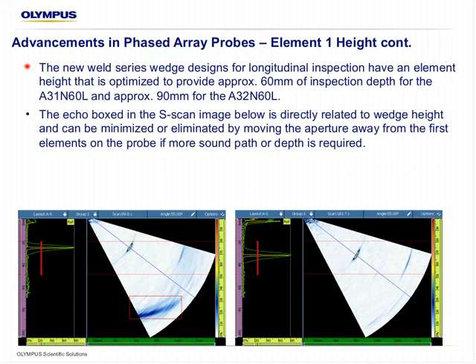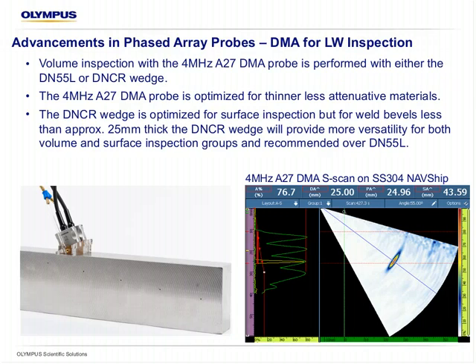The new Weld series L-wave wedges are designed to have an element height that is optimized to provide a 60-millimeter inspection depth for the smaller A31 probe and a 90-millimeter inspection for the larger A32 probe. These are always going to be a compromise between height of the element and interference from the wedge at some depth. And again, within the advertised range, we see a very high quality S-scan free of some of the adverse wedge echoes in earlier models. The DMA matrix array probes are overwhelmingly recommended for any L-wave application now. As soon as you separate the transmitter and the receiver, it removes all wedge considerations from the equation, including the height of the first element, wedge dampening, all of that goes away.